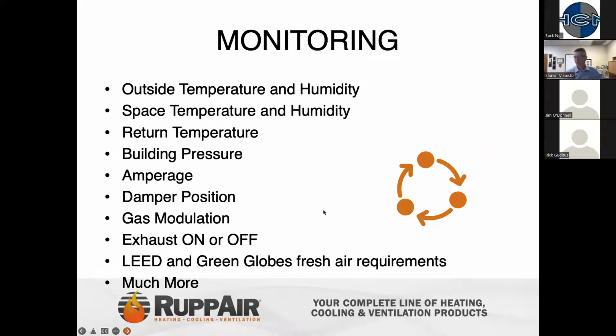Within the monitoring, you're going to get everything from outside air temperature and humidity, space temperature and humidity, return temperatures, building pressure, amperages off the equipment, damper positions, how they sit, gas modulation, if exhaust fans are on or off, and also the benefit of meeting LEED and green globe fresh air requirements. So we'll have alerts on there if you're not moving the fresh air needed to meet those requirements, having LEED or green globe, and a lot more.